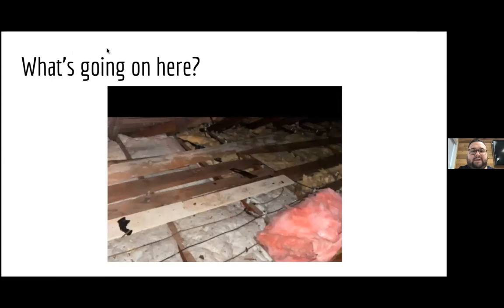So does anybody know what's going on here? It's a terrible photo, unfortunately, but. Yeah, wires line across wood. In the attic. Not an insulator. Yeah. In the insulation. Yeah. So even worse, this is actually knob and tube wiring, the dreaded knob and tube wiring that's laying directly on insulation, which is a huge concern because essentially the way knob and tube works is it's not insulated wire like we use today. Knob and tube disperses the heat that's generated by the wiring just freely into the air. And so when people do renovations and upgrades down the road and don't realize this, a lot of the time they're blowing insulation up into their attic and things like that. And then it's it's landing in contact with these wires, which, again, can be a hazard, right? It can be an electrical hazard. I see a couple other building code violations in there, too.